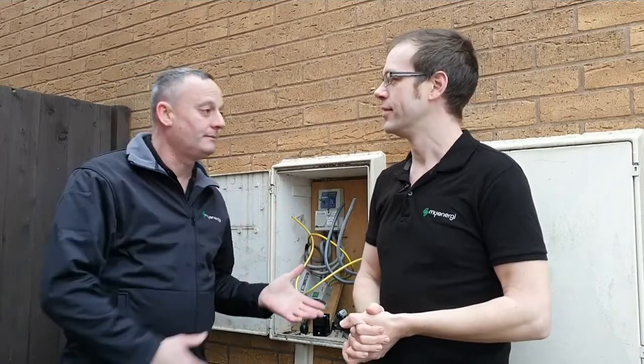So at the point in the installation now where we need to connect these new 25mm squared meter tails and 16mm earthing conductor from a consumer unit to the incoming supply, Joe. What does that really mean? So basically we're going to be splitting the tails, and of course we know that we're going to be fitting these fixed connector blocks into the back of here, popularly known as Henley blocks, and then we're going to reposition some of the tails while taking a supply out to our new consumer unit.